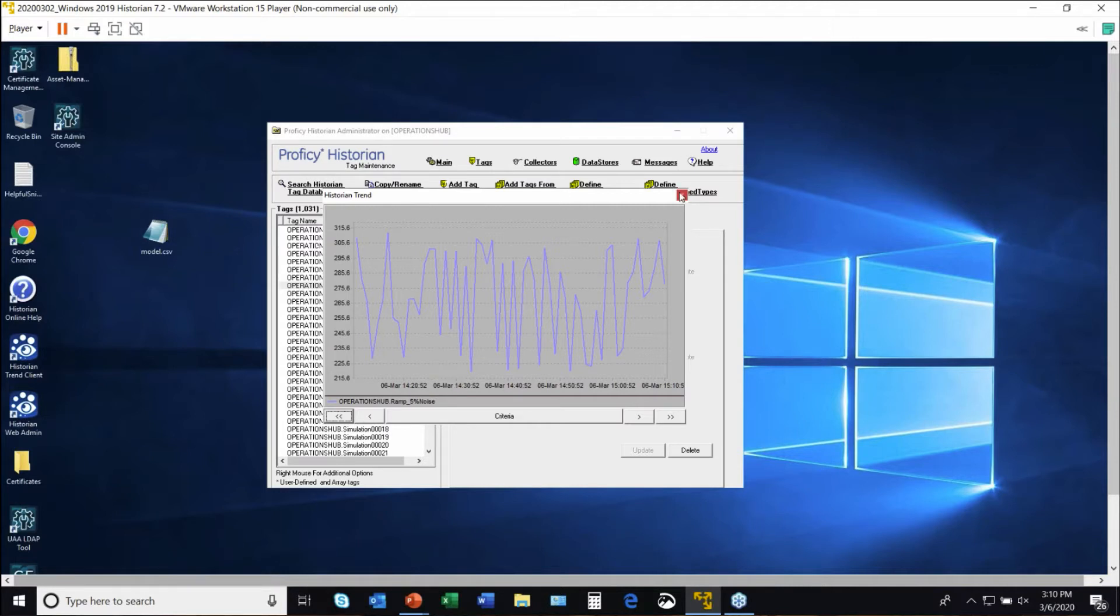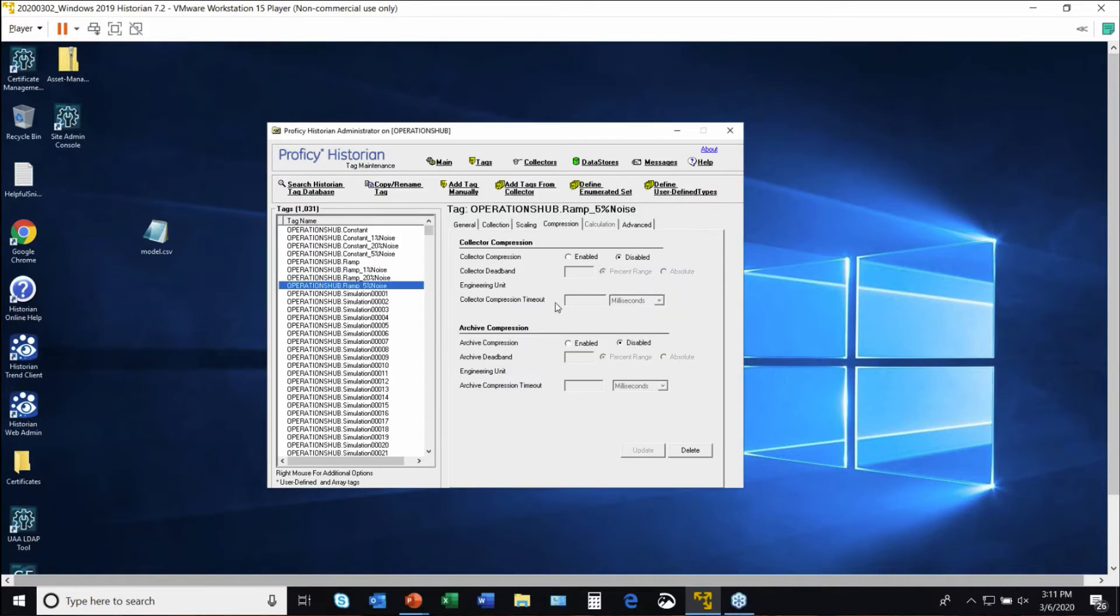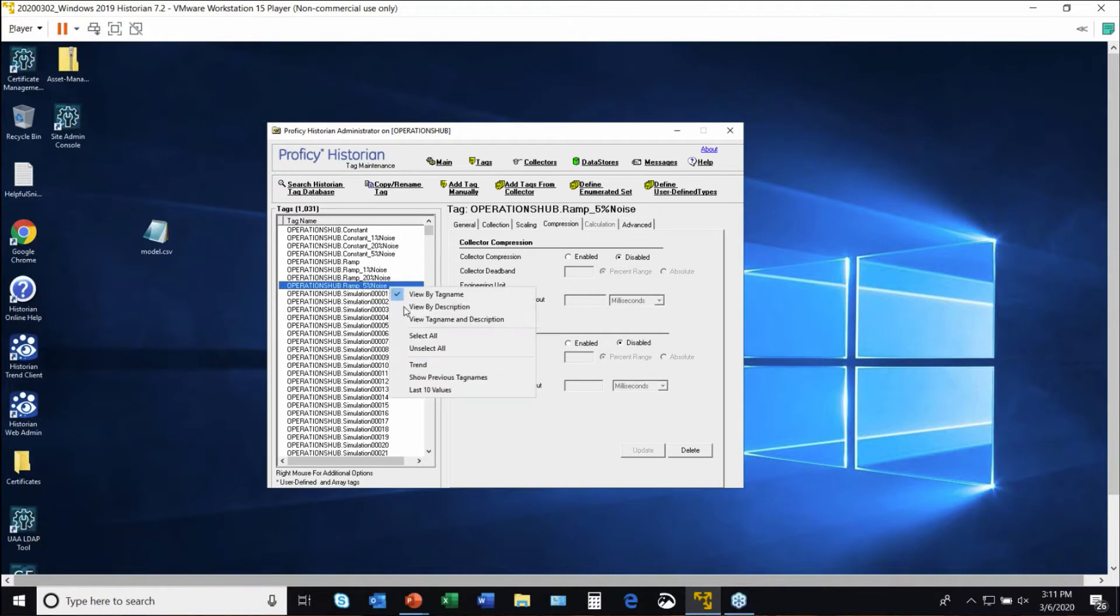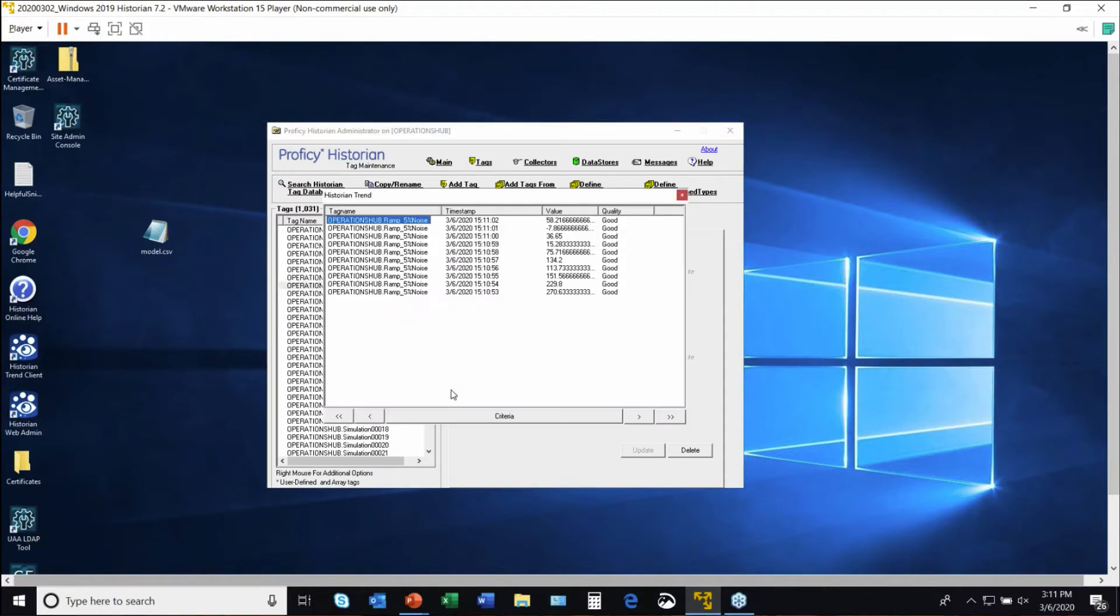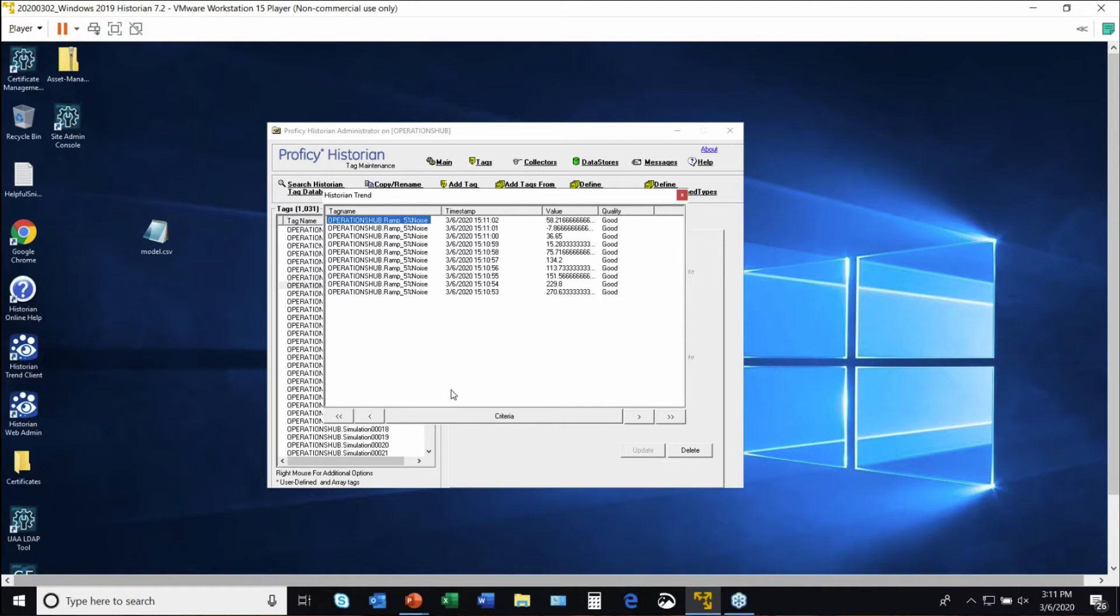As I'm wringing out the system, I've got somebody looking at the PLC or at an HMI screen. At a given point in time, I know what the value was on that HMI screen. Have I actually mapped this tag correctly into my historian?